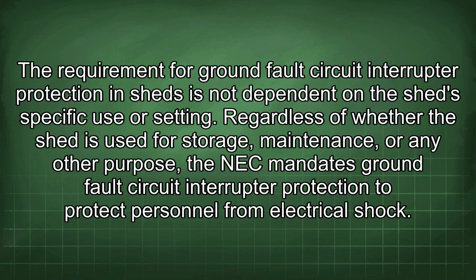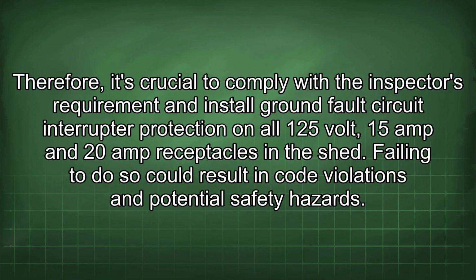The requirement for ground fault circuit interrupter protection in sheds is not dependent on the shed's specific use or setting. Regardless of whether the shed is used for storage, maintenance, or any other purpose, the NEC mandates ground fault circuit interrupter protection to protect personnel from electrical shock. Therefore, it's crucial to comply with the inspector's requirement and install ground fault circuit interrupter protection on all 125-volt, 15-amp and 20-amp receptacles in the shed. Failing to do so could result in code violations and potential safety hazards.